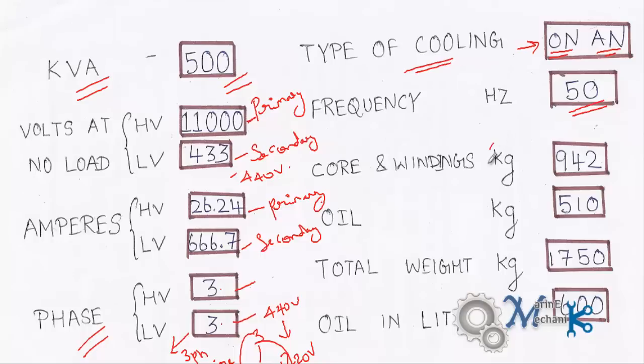And the weight of individual components is given here. The core and winding leading weight is 942 kg, just some short of a ton. Oil weight is 510 kg. Oil in liters is also given. You can see the difference: 600 liters and 510 kg. And the total weight of the transformer for transportation and handling purpose.